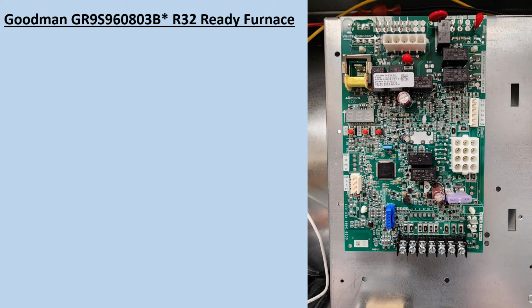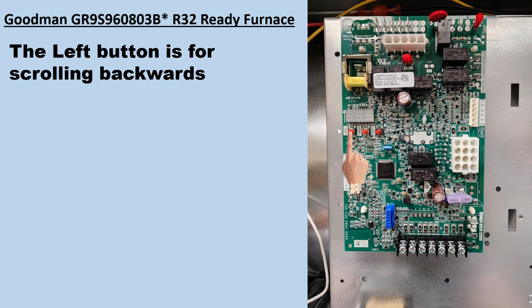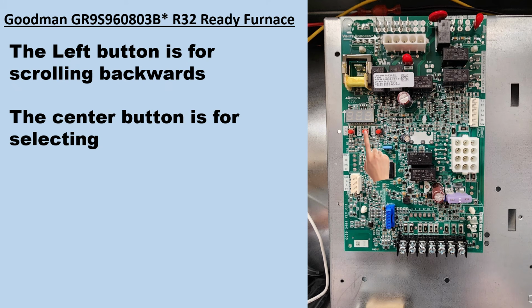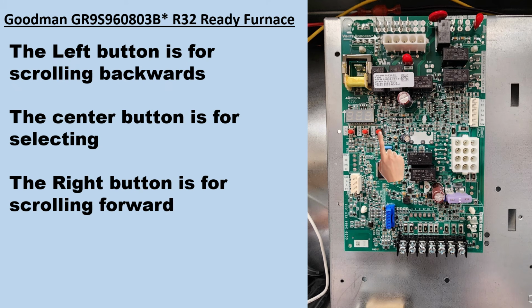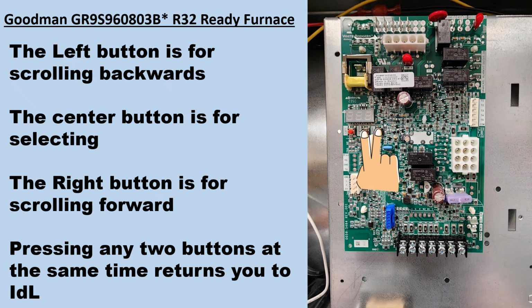So on this unit, the Goodman GR9S960803B R32 ready furnace, the left button is for scrolling backwards, and you find these buttons on the board right under your 7-segment LED board. The center button is for selecting, and the right button is for scrolling forward. Pressing any two buttons at the same time returns you to IDL, idle, which means there's no call on the unit.